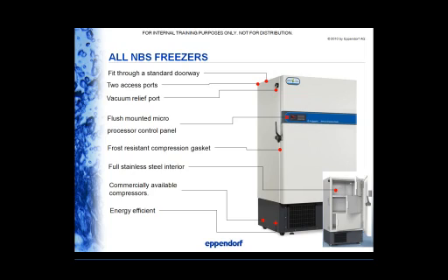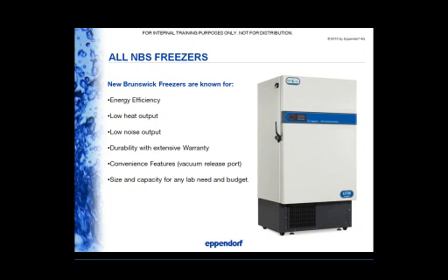All the compressors and refrigerants are commercially available, so they can be purchased from any supplier. It doesn't have to be directly purchased from NBS or through Eppendorf. And of course, all of our freezer lines are energy efficient, with the HEF line being most energy efficient. And finally, to put it all together, New Brunswick is known for energy efficiency throughout the whole breadth of the product line. Low heat output, low noise output. We have also one of the most durable freezers on the market, which we can back up with our warranty plan. We have unique convenience features, just like the vacuum relief port, and of course we have a large range of sizes to satisfy any capacity and any budget.